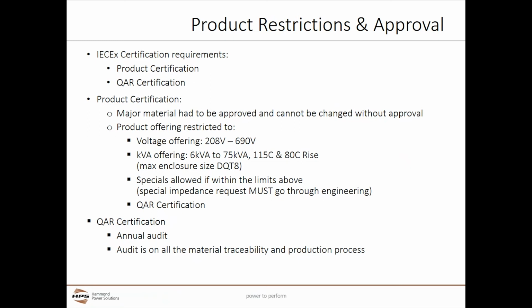The actual IECEx certification requirements do require the product to be certified and operate within parameters of the hazardous location, but also it requires QAR certification. In regards to product certification, all the major materials have to be approved and cannot be changed without prior approval. The voltages that we offer are between 208 volts and a maximum of 690 volts. The kVA offering is between 6 and a maximum of 75 kVA, or the typical enclosure that would be equivalent in the approval is the DQT8, which does 75 kVA at 80-degree rise. That's what the certificate covers, nothing outside of this approval.